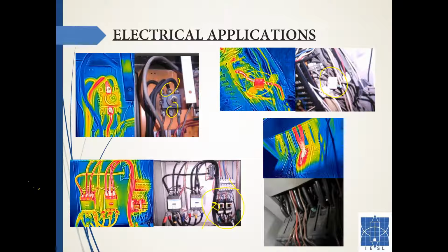All right, the last image. This is really visually clear. You can see the copper oxide right here, and thermally what we see, right? So these situations were the ones I was talking about. You don't know whether this is a loose connection or a tight connection. To make sure, you have to remove this. You have to take this out, and you need to clean it. You need to clean the terminal, maybe cut out a little bit, and you need to clean the contactor terminal as well. You need to clean both ends and put it back, and do the follow-up survey, of course.